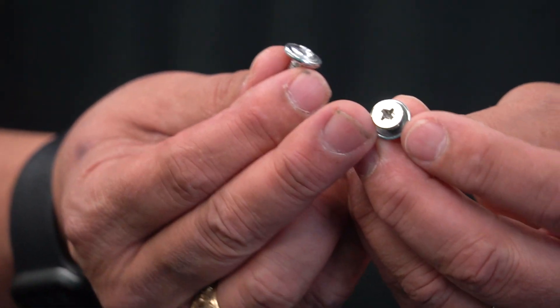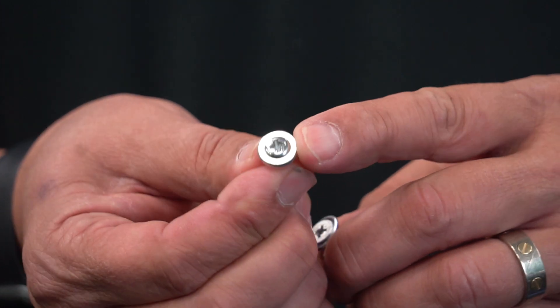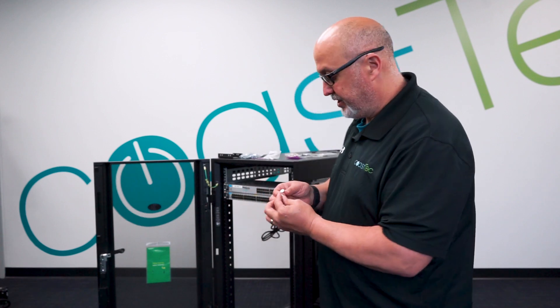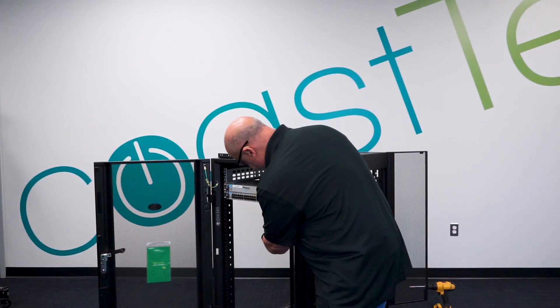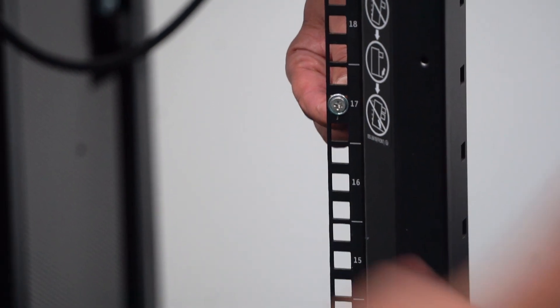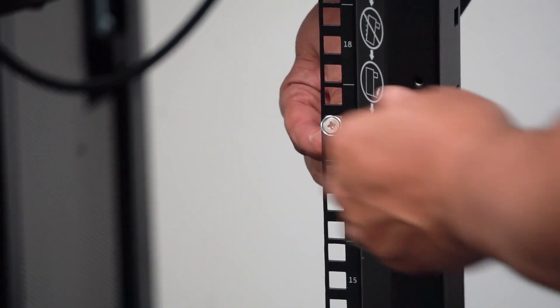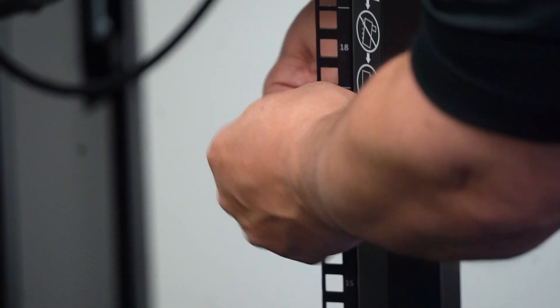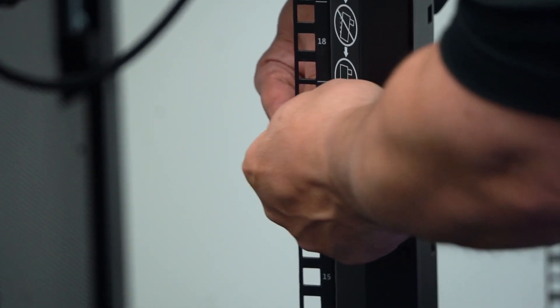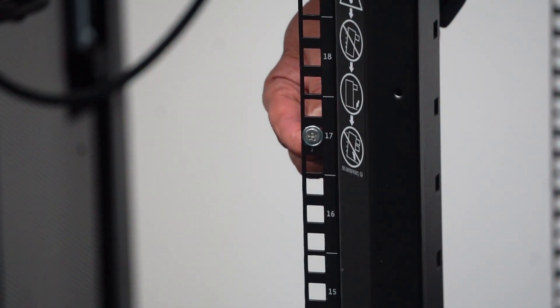When you open up the rail kit package, there are going to be two different types of screws: a screw that has a crush washer that's loose, and a screw that has a built-in stable washer. The crush washer screw is the one you're going to use to attach the rail kit to the cabinet. On the front of the cabinet there are square holes — the crush washer gets centered on that square hole to mount the rail kit. The rail kit comes up from behind, and you might think something is wrong because the screws don't go through those holes, but when they're centered, the crush washer will crush and keep it in there nice and firm and tight.